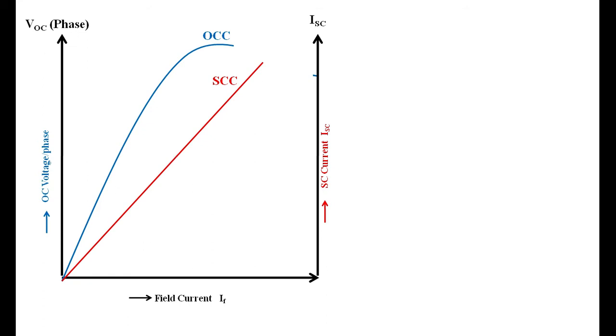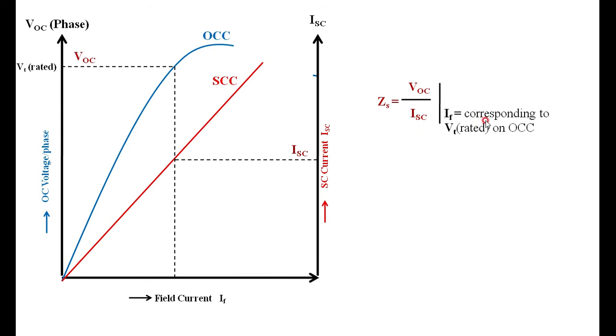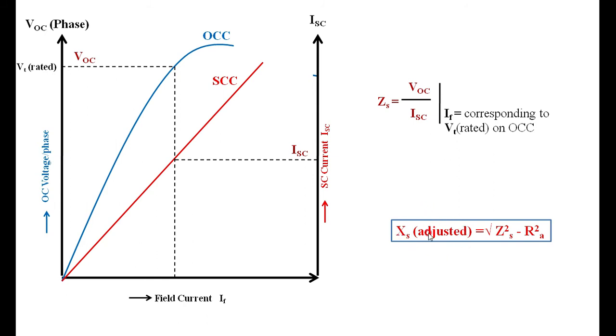To determine the synchronous impedance, corresponding to the rated voltage, mark the point on the OCC and find out what field current is required to generate that rated voltage under open circuit. For the same field current, note the short circuit current. Then, VOC divided by ISC for the same field current gives the synchronous impedance Zs. Then Ra is subtracted to find Xs, which is called Xs-saturated.